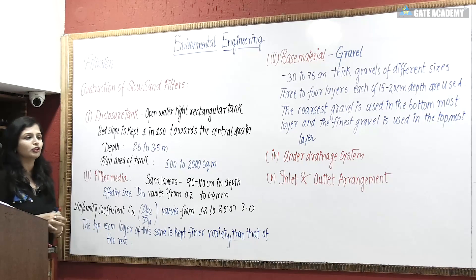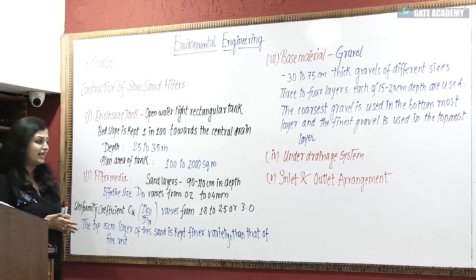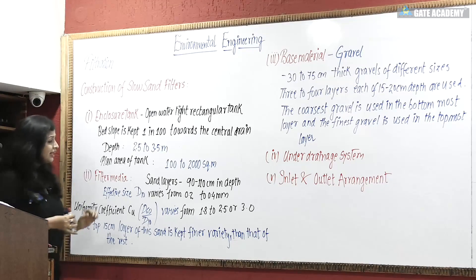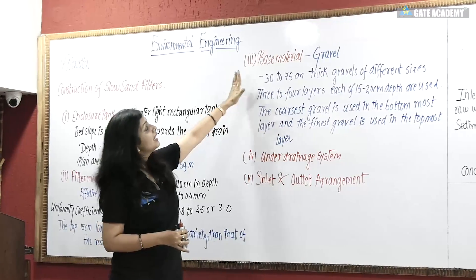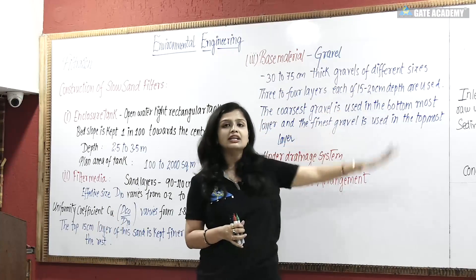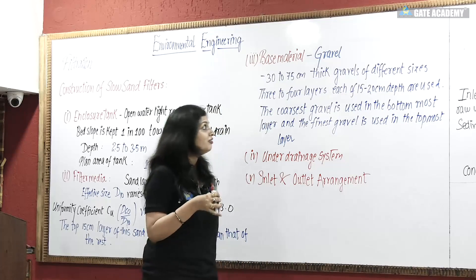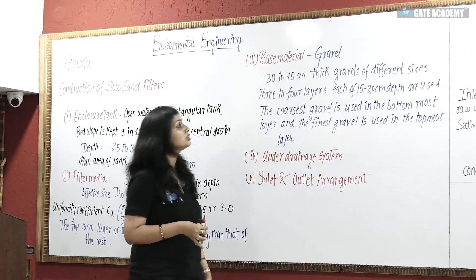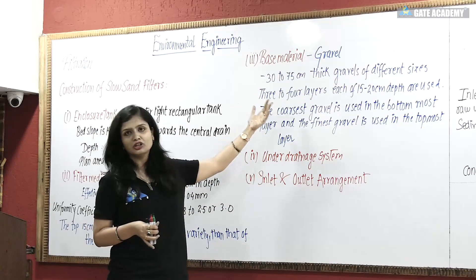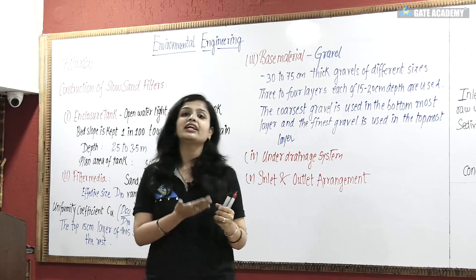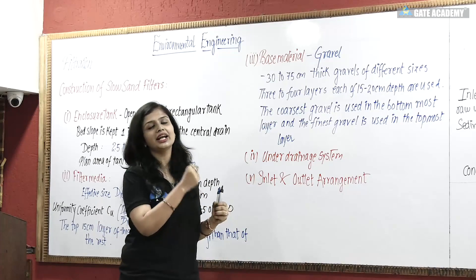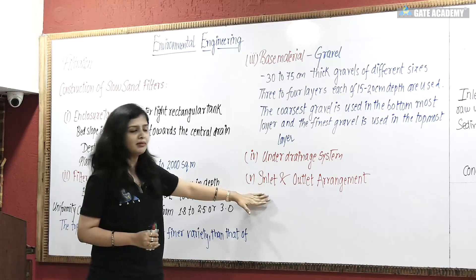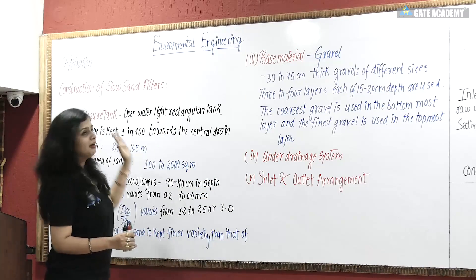The top 15 cm layer of sand is of the finer variety — its particle size is very small. For the base material gravel: it is 30 to 75 cm thick. There are 3 to 4 layers each of 15 to 20 cm depth. The coarse gravel layer is at the bottom and the finest gravel layer is at the top. One function of gravel is that it supports the sand layers. The gravel is below the lateral drains and main drain — this is the under drainage system, consisting of lateral drains and the main central drain, along with the inlet and outlet arrangement.